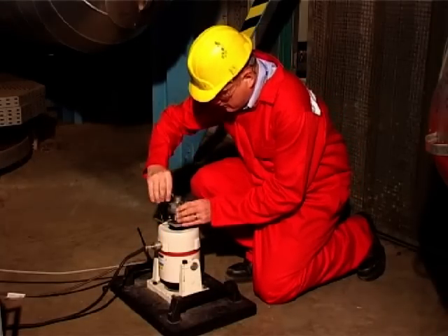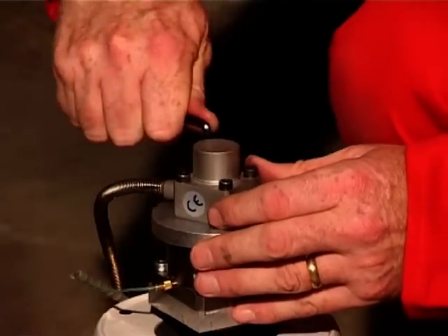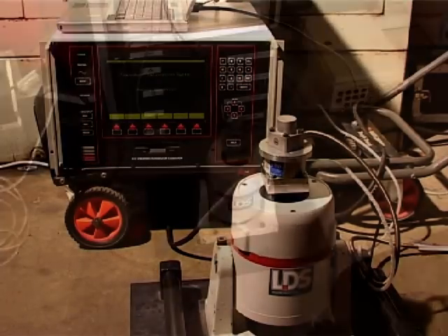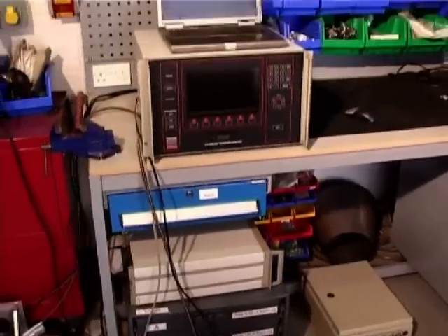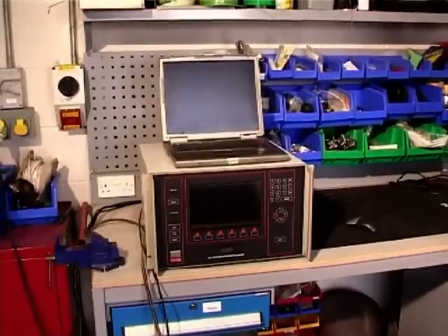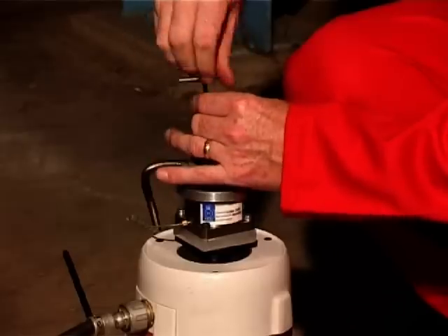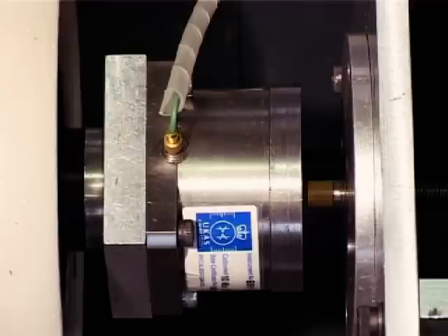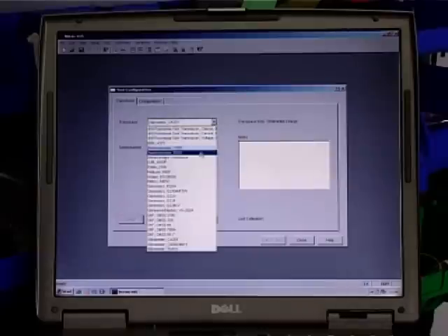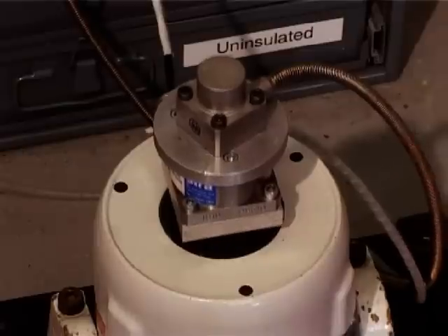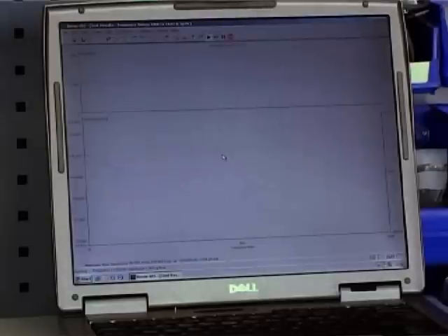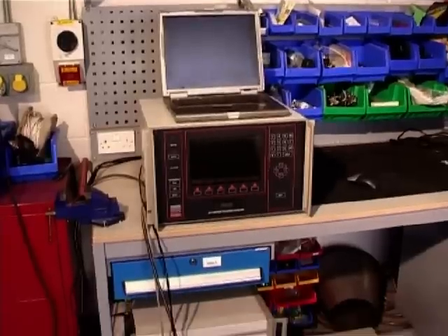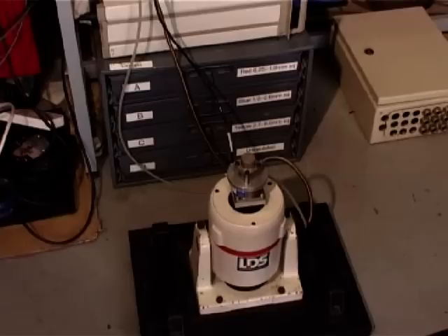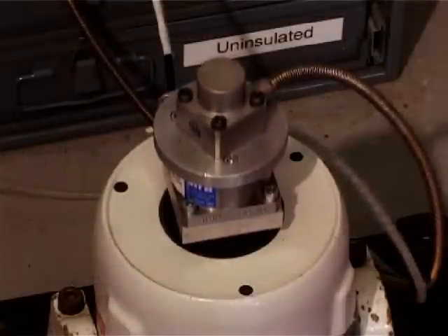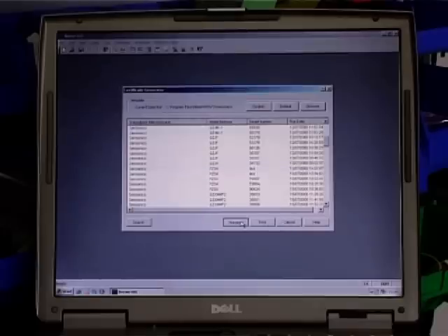Normally, the technician takes the Beran TransCal system to each transducer location and connects the shaker and reference sensor to the main unit. Or alternatively, if all the sensors have been removed for an outage, they may be brought to the system based in a workshop. Accelerometers and velocity sensors are directly mounted onto the reference and connected to the TransCal system, while proximity probes use an additional fixture. The transducer type and serial number is selected from a database, and the calibration tests automatically run in sequence. On completion, the results can be printed into a user-defined certificate format or stored for batch plotting later.